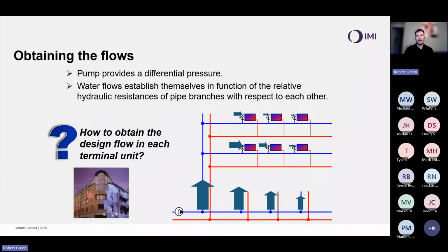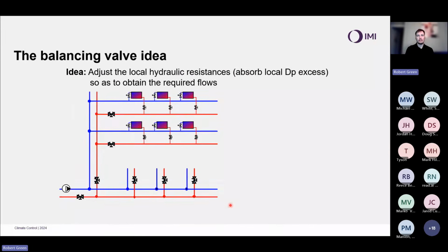And that's actually where the balancing valve comes in, because most of these imbalances are due to the difference in pressure loss for different sections of the pipe, because we are losing pressure as we go down there. So the idea with a balancing valve is we wish to adjust the local hydronic resistances, absorbing the excess differential pressure to obtain the required flows. Now in a sentence that sounds fairly simple, but we're going to look at how we do that.